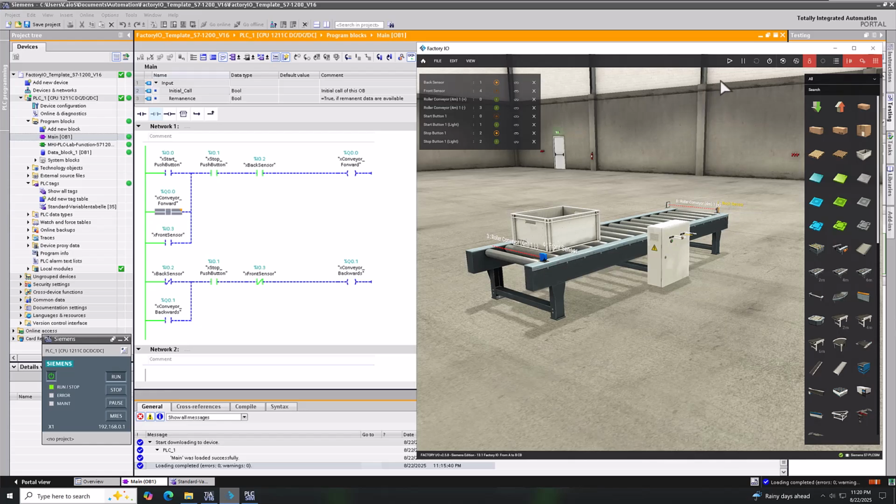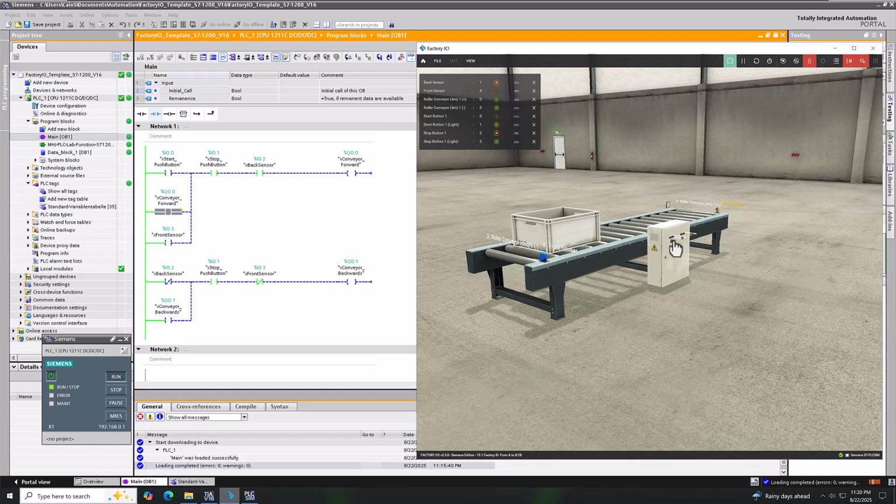And then if we go to run this, we can easily see, if I can hit that button from here, how the logic works. It's very simple, especially with no speed commands, forward or reverse, no analog. You don't have any one shots or anything like that. You just basically seal in circuits and then drop in and out based upon the sensor itself that you're using.